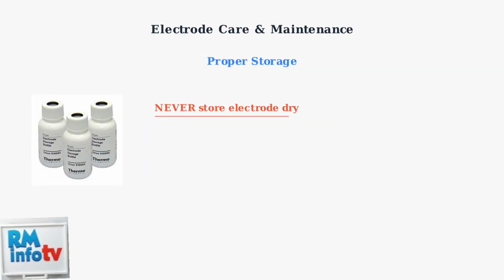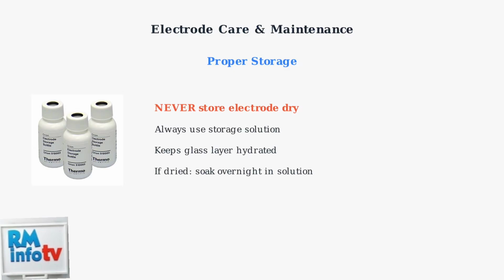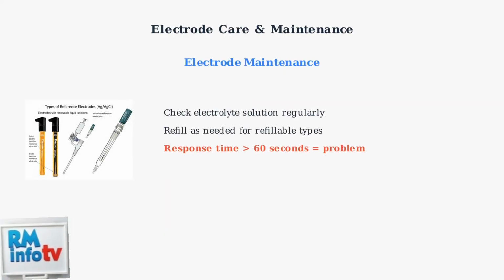Never store the electrode dry. Always use a storage solution to keep the glass layer hydrated. If the electrode dries out, soak it overnight in storage solution to restore proper function. For refillable electrodes, regularly check and refill the electrolyte solution as needed. A slow response time longer than 60 seconds indicates an old or dirty electrode that needs attention or replacement.